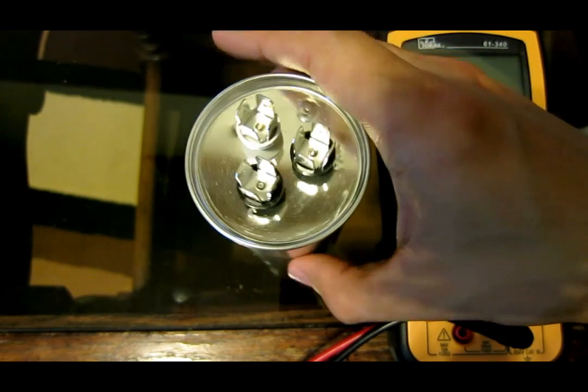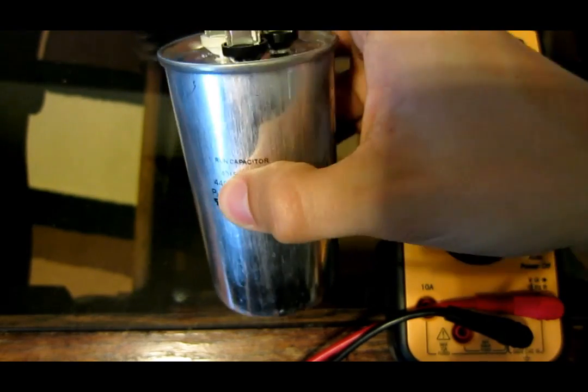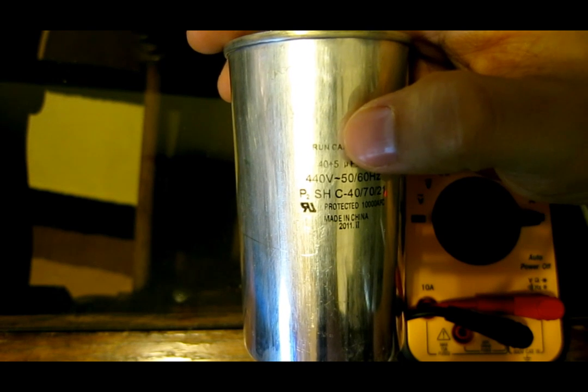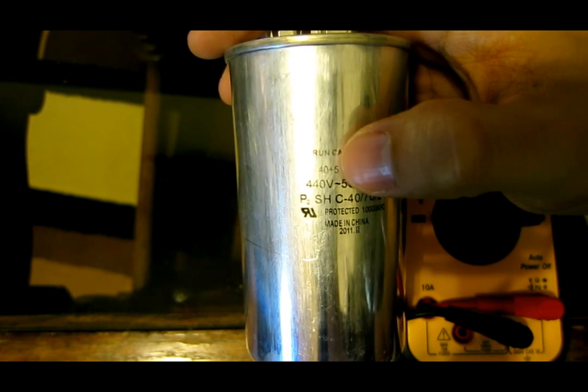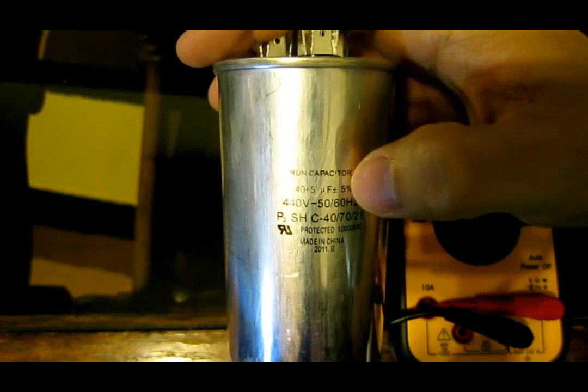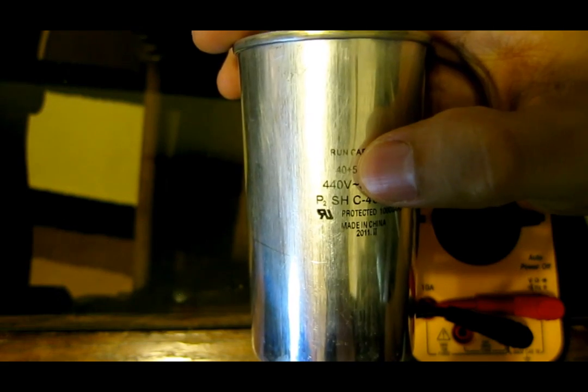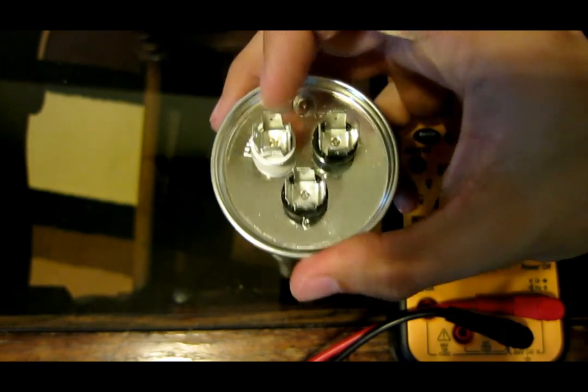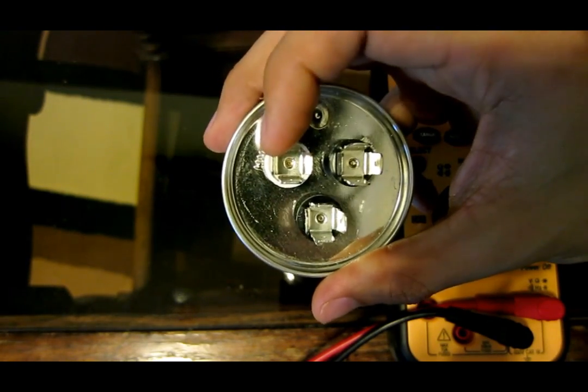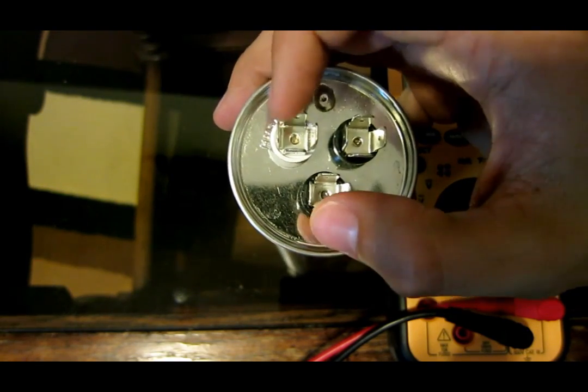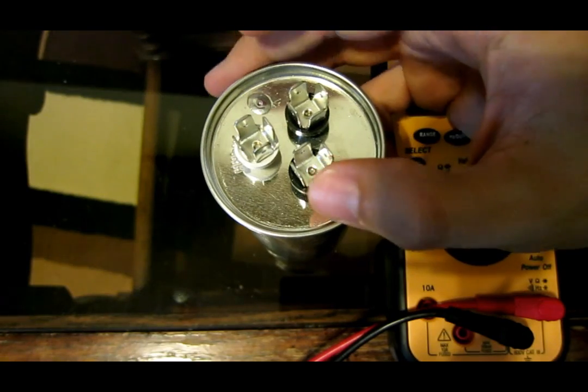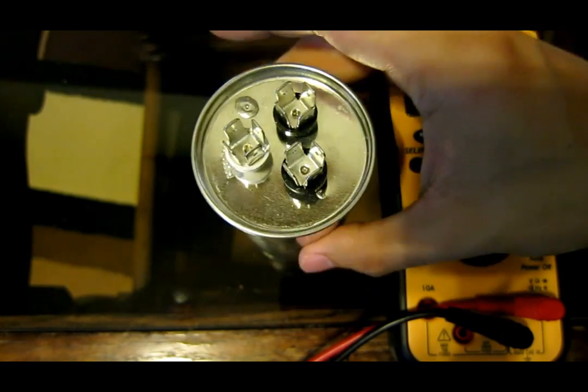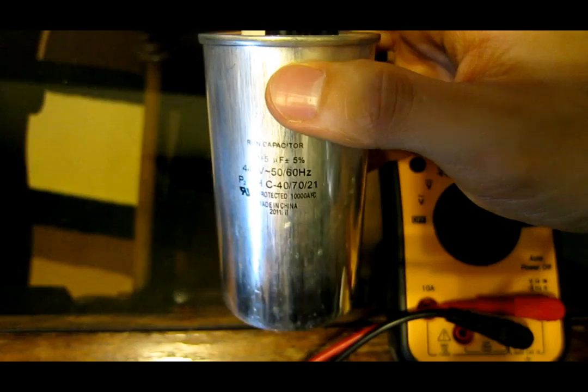Whenever you buy these run capacitors, you want to get the correct capacitance. Right here, you can see, right there, it says 40 plus 5. It doesn't mean 40 add 5, it means 40 and 5. That's microfarad. It's 40 microfarad and 5 microfarad. The 40 goes between common and the compressor, hermetic, right here. These two, in a second when I measure it, should be 40 microfarads. And right here, from common to FAN, should be 5 microfarads. And it should be within 5% tolerance.